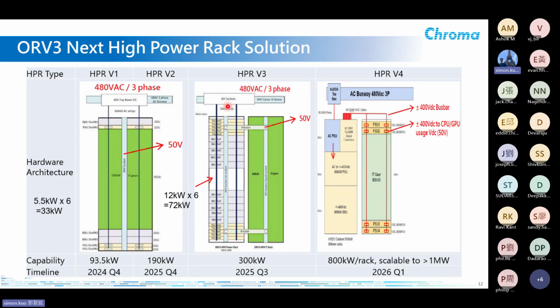The previous slide was from the electrical point of view, and this slide shows the mechanical point of view of how it changes. In the past, on the left, we had everything in the same rack running under 50 volts. Then on V3, the sidecar was proposed, so you have the BBU and power shelves in the same rack, and the IT computing rack at the side, with the transmission still running at 50 volts.